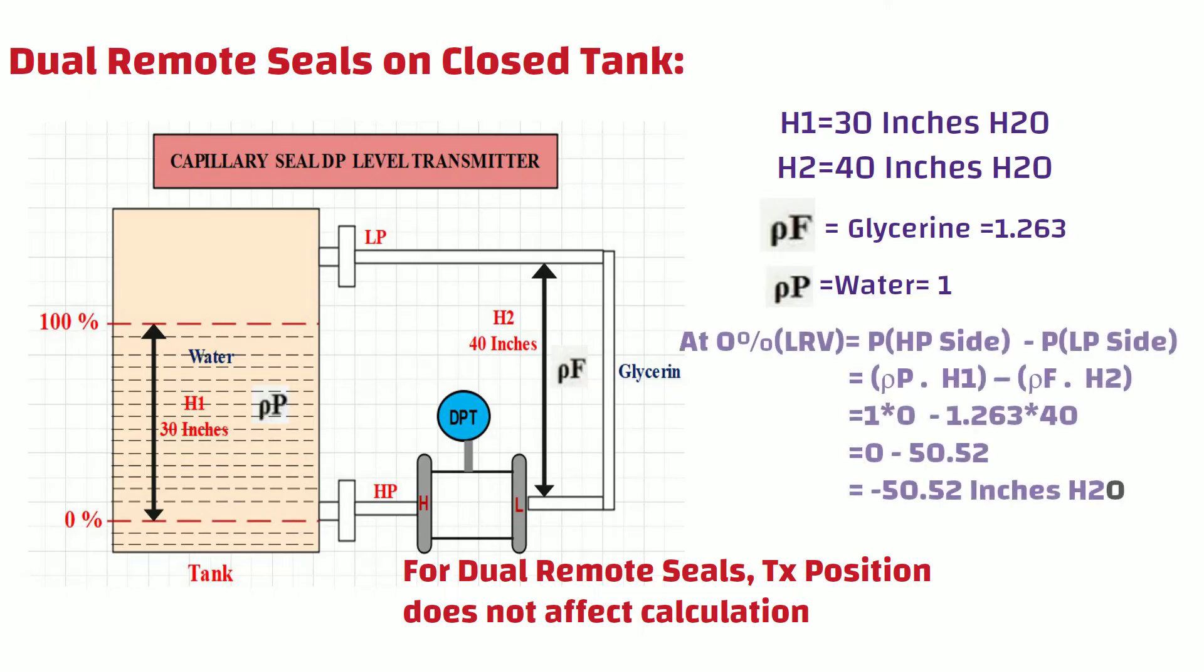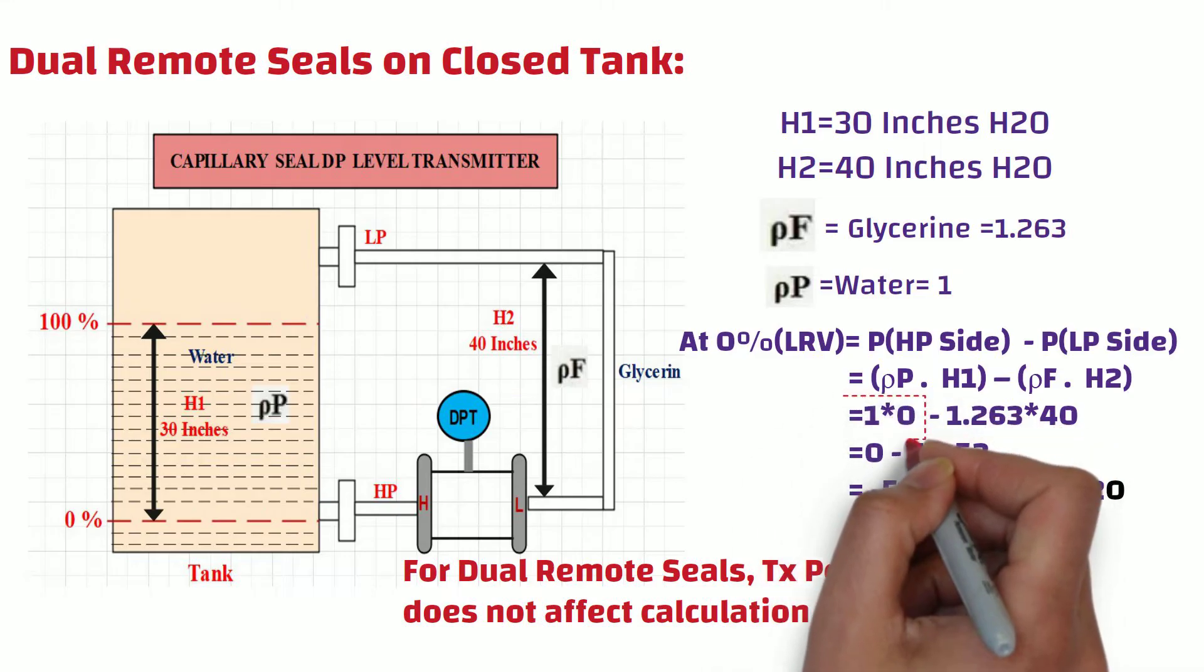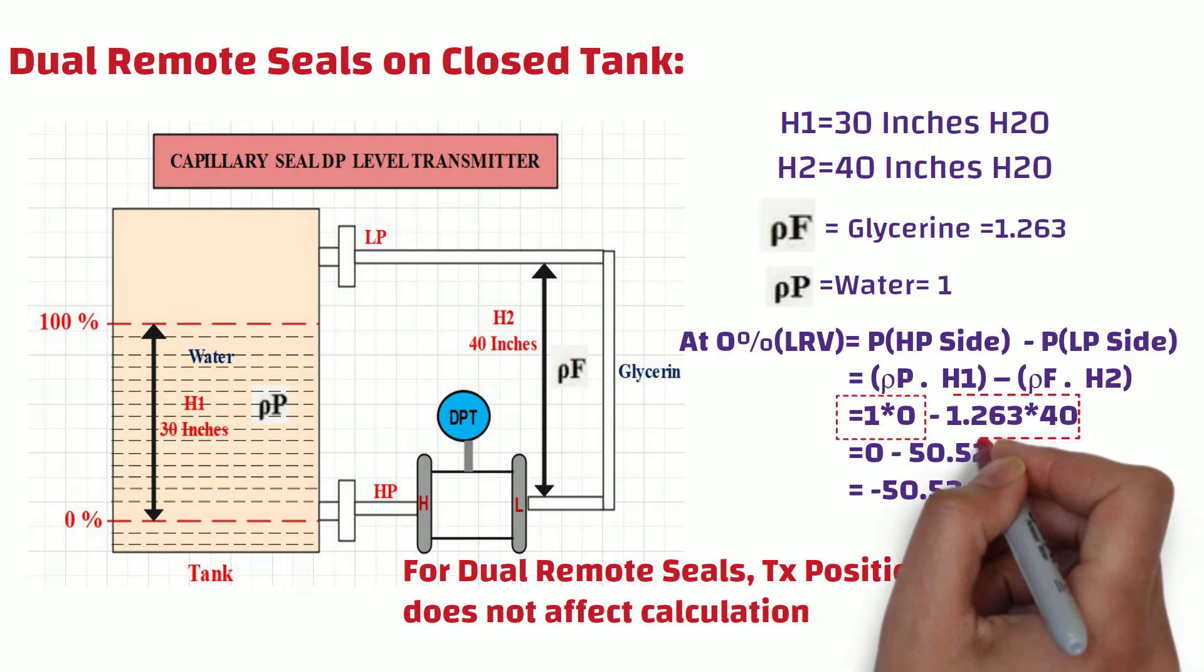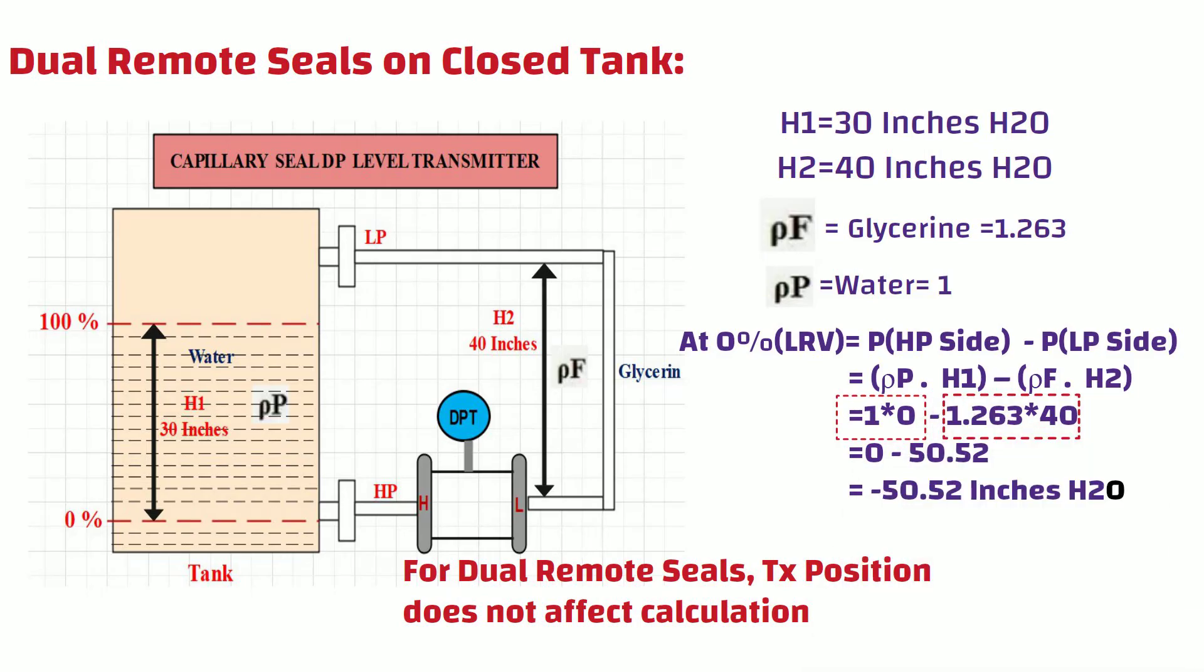So at 0% or at minimum level, the DP transmitter high side has 0 inches H2O pressure, which is multiplied with the specific gravity of water, which gives 0 inches H2O. At the same time, the DP transmitter low side port has 40 inches H2O pressure, which multiplies with the specific gravity of glycerin. In this case, the differential pressure is minus 50.52 inches H2O at 0% level or at minimum level. And this is our lower range value in this example.